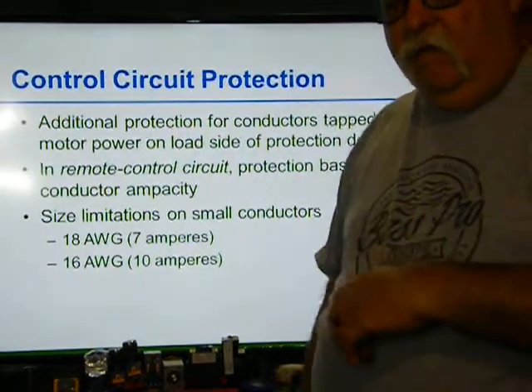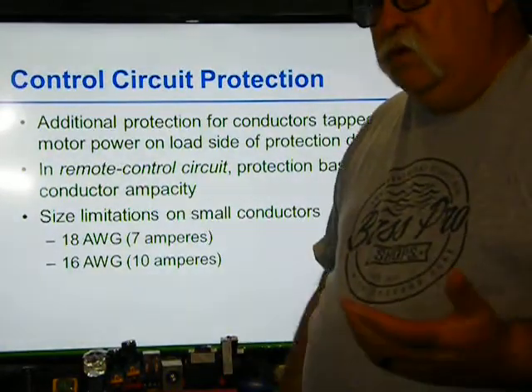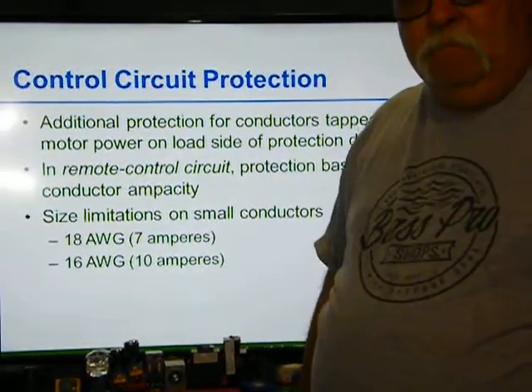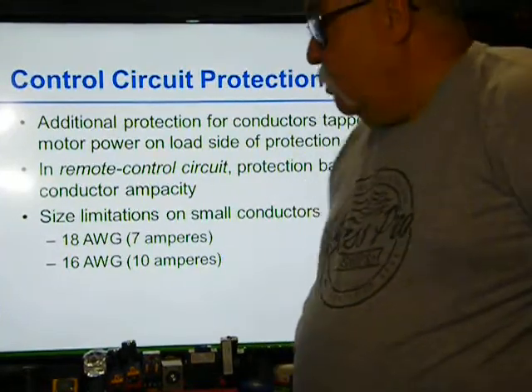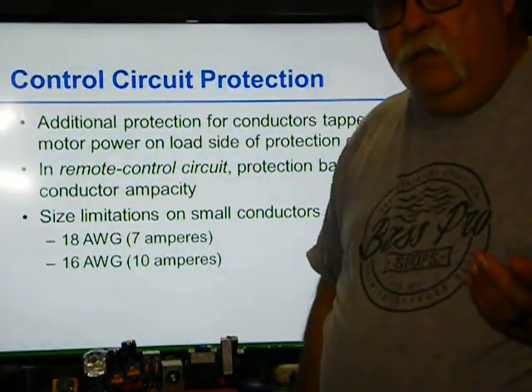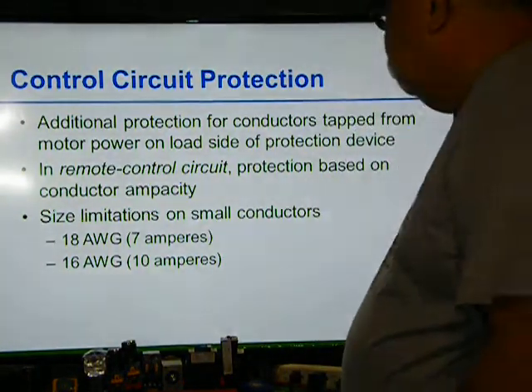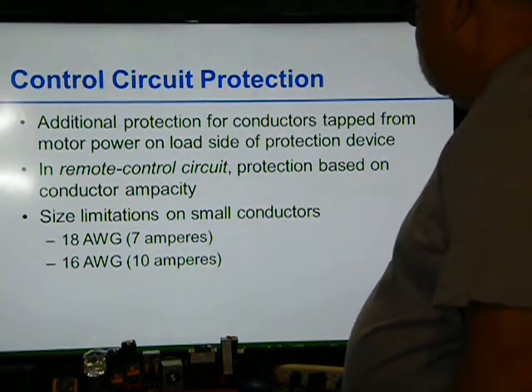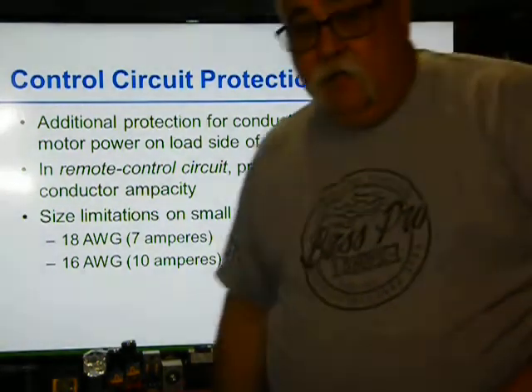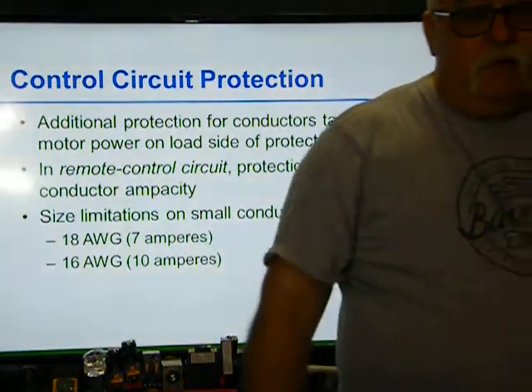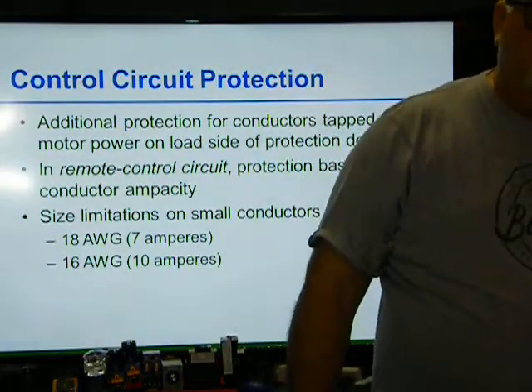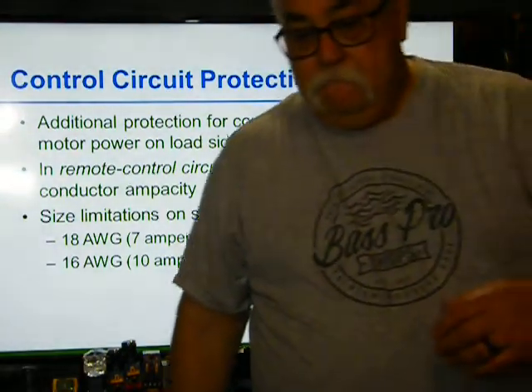Again, if it's coming off a transformer within the motor control, they're talking about 50 watts. So there's not really a lot of load on it, so that's why we don't have to derate the conductors per control circuit. Remote control circuit protection is based on the conductor ampacity. So if I've got a 14 gauge wire going across, I've got a 15 amp breaker. I've got a 12 gauge wire going across, I've got a 20 amp breaker. And you size it accordingly.